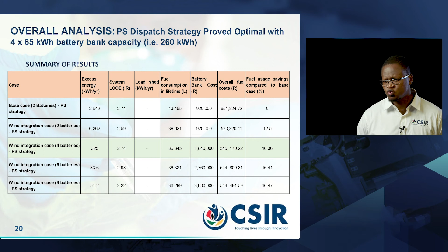Further on, we looked at the predictive dispatch strategy algorithm in terms of implementation, how it was supposed to be implemented on the ground. So we designed a logic diagram for this, which constituted a reserve margin for the algorithm. As we recall, the predictive dispatch strategy definition says the algorithm is aware of future load demand, with a foresight of 48 hours, and aims to maximize self-consumption of excess energy so that energy curtailment can be minimized. So we defined a reserve margin for the forecast such that there is about a 30% reserve.